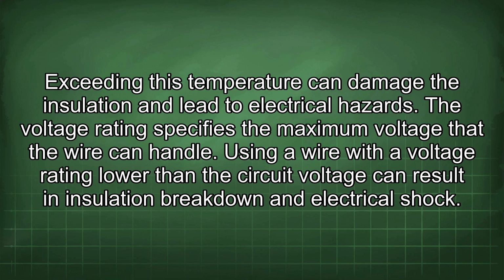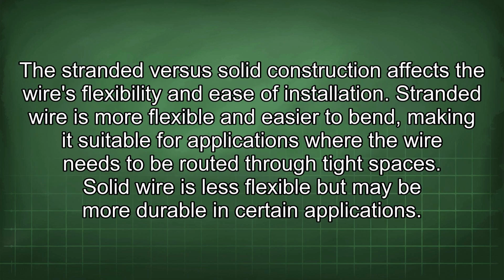The voltage rating specifies the maximum voltage that the wire can handle. Using a wire with a voltage rating lower than the circuit voltage can result in insulation breakdown and electrical shock. The stranded versus solid construction affects the wire's flexibility and ease of installation. Stranded wire is more flexible and easier to bend, making it suitable for applications where the wire needs to be routed through tight spaces. Solid wire is less flexible but may be more durable in certain applications.